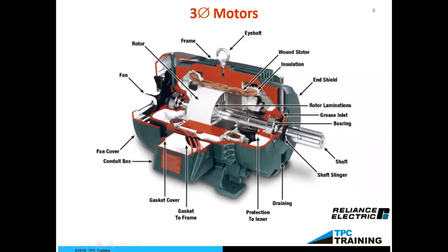And even on a 1 horsepower motor, which is a fairly small motor, we can't even put our hand on that shaft and try to stop it. That's how powerful that magnetic field is. A few more parts that we are going to see here. We can see the stator and the rotor very easily. But then we have a fan over here on the left-hand side, way near the end. And that fan is going to help cool the windings in the motor.